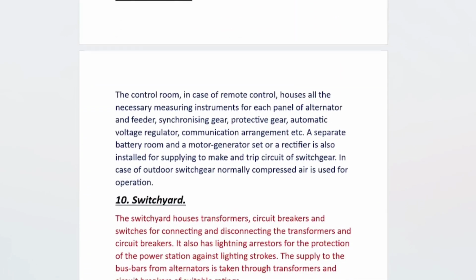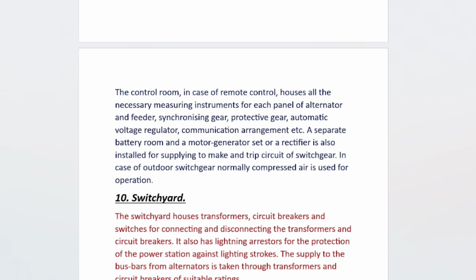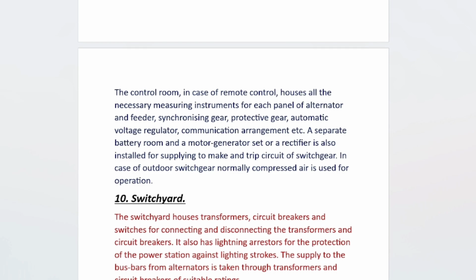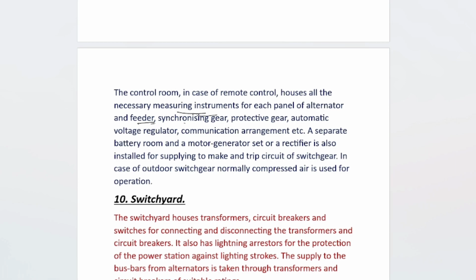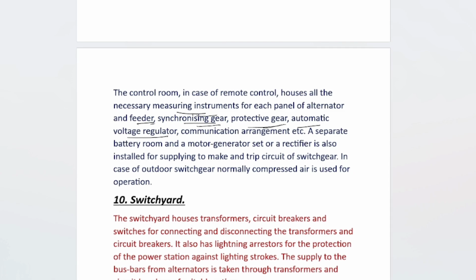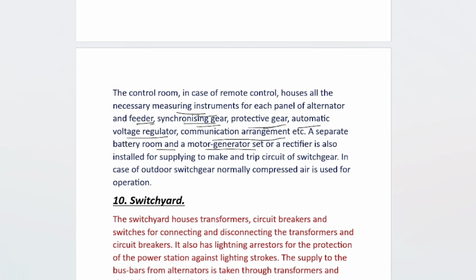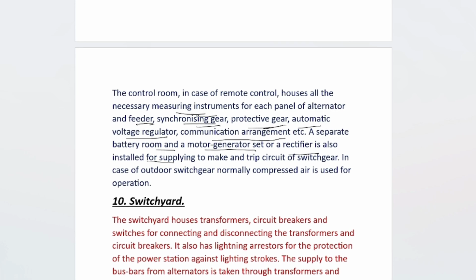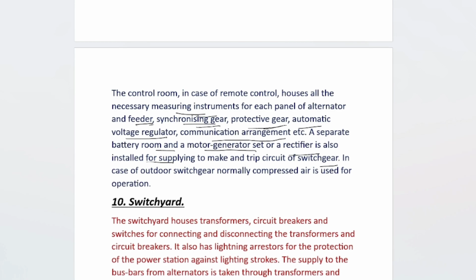Next part is the control room. In the case of remote control, it houses all the necessary measuring instruments for each panel of alternator and feeder, synchronizing gear, protective gear, automatic voltage regulator (AVR), communication arrangement, etc. A separate battery room, motor generator set or a rectifier is also installed for supplying the make and trip circuit of switchgear. In the case of outdoor switchgear, normally compressed air is used for operation.